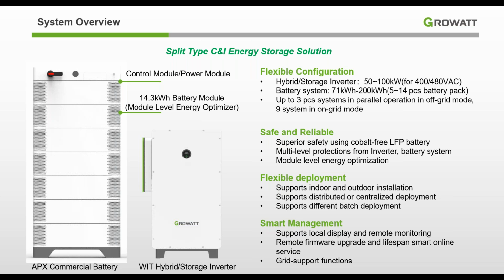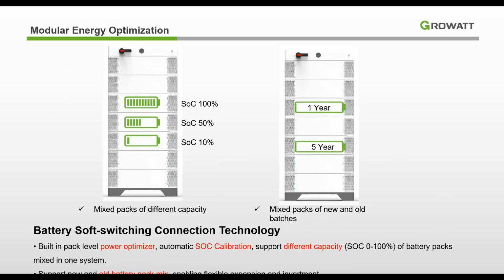Module-level energy optimizer. So this is similar to the APX, the high voltage one. It's a built-in pack level power optimizer. So that means the battery will automatically self-balance by itself once the system has been connected. Even if you mix them in different SOC, it just doesn't really matter. And even with the voltage difference, it will force charge by itself. Since the optimizer is here, now you can even mix new and old batteries.